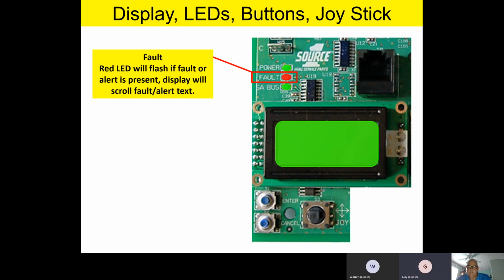Hey, Joe, on the faults, how long do they last? How do you clear them? How do you clear what, the fault? Yes. That's a good question. It's really going to depend on the fault or the alert. Most of them will clear themselves. Let's say, for instance, I've got a sensor fault. If I replace that sensor and power the board back up, it'll see that the sensor is working again, and it'll clear itself. So most of the time, it'll fix itself.